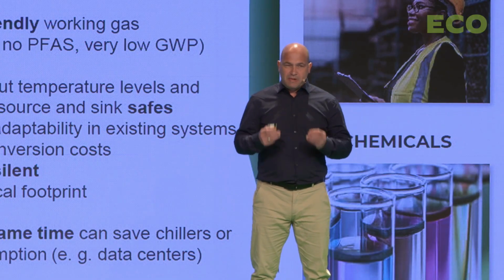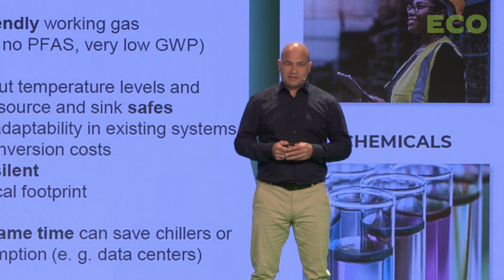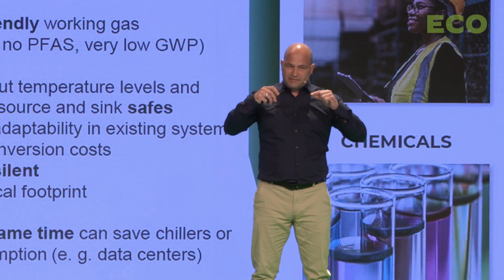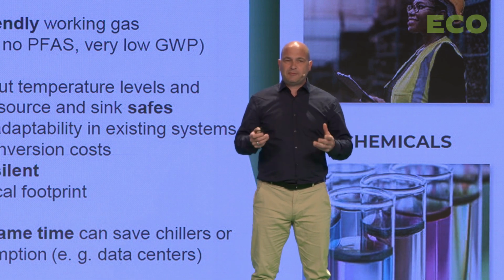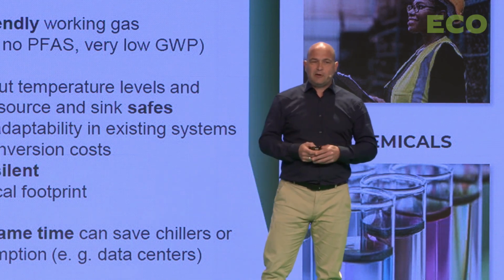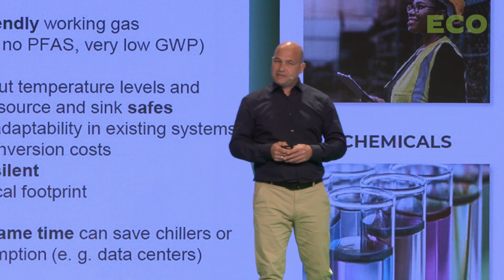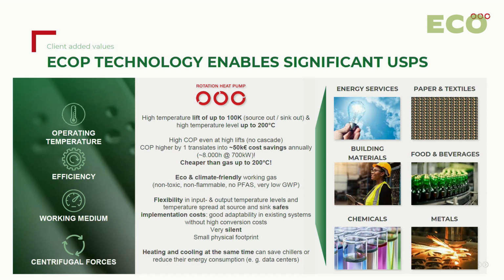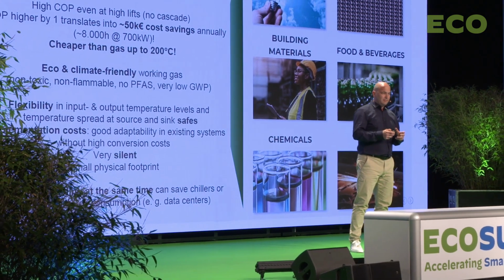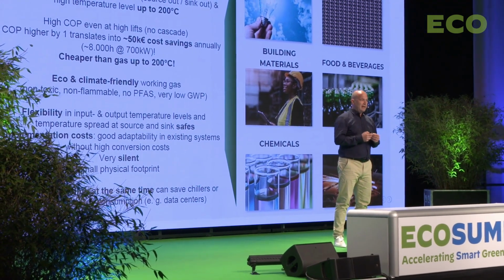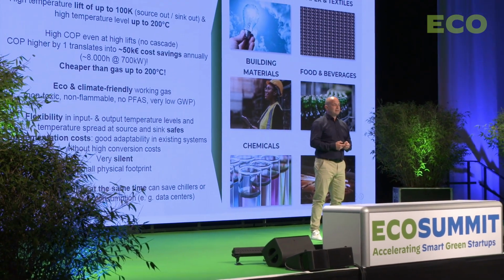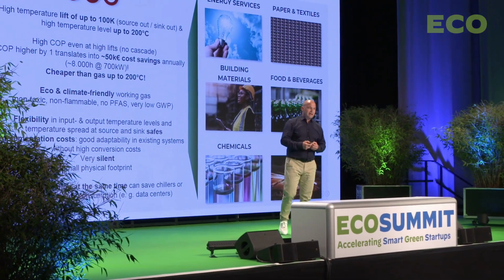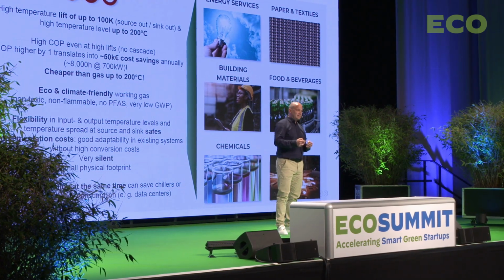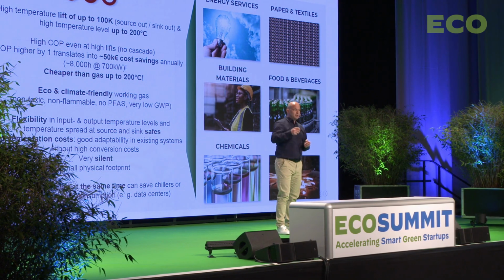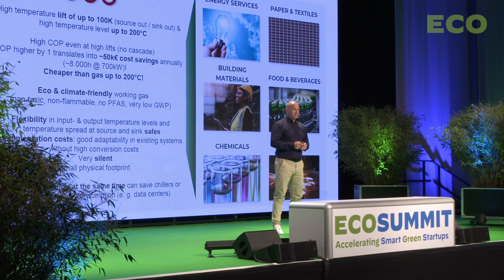The merits of this technology: first, because it's a function of rotation speed, we can realize lifts of up to 100K, reaching output temperatures of up to 200 degrees C, which is exceptional, including steam production. Second, and even more important, we can realize high lifts with still high COPs, and that's what drives the business case. If you go to a cascaded system with two machines in a row, you lose your COP all of a sudden.